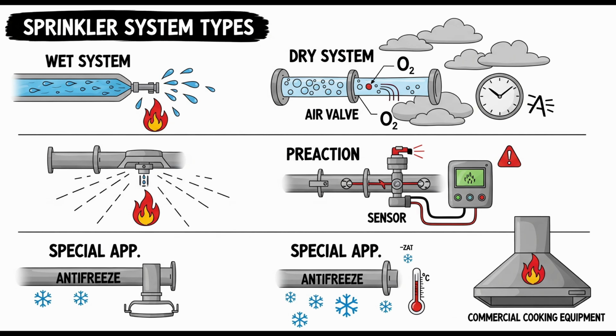Exactly. And because of that necessary delay, monitoring and managing the system's air pressure is absolutely critical. Pressure gauges are required in many locations. More gauges. Where do they go on a dry system? You need them on both the water side and the air side of the dry pipe valve itself. Okay, checks and balances on the valve itself. Precisely. To confirm the water supply is ready and the air barrier is holding. You also need gauges at the air compressor, the air receiver, if there is one, in each independent pipe connecting the air supply to the dry pipe system, and at any quick opening devices.